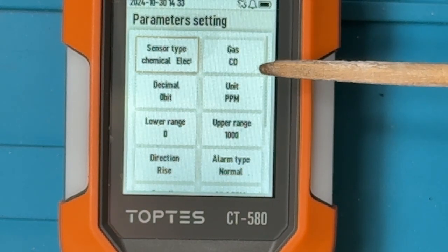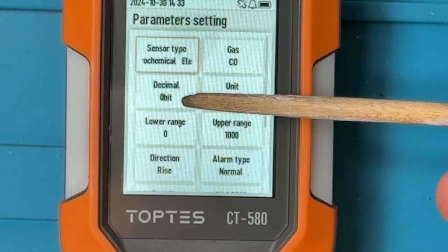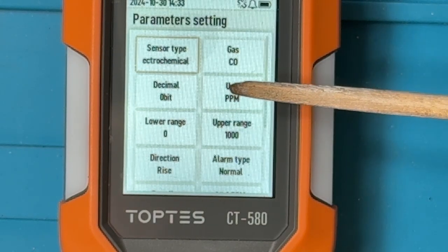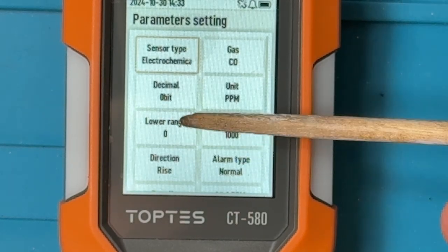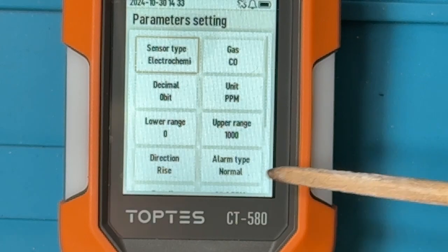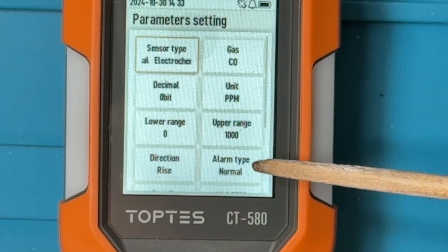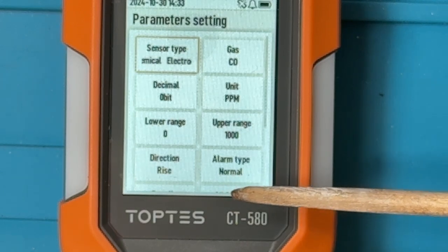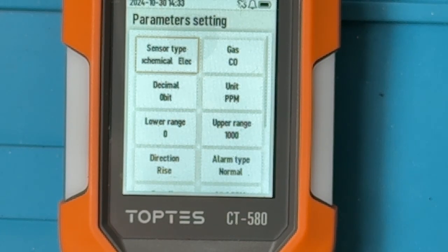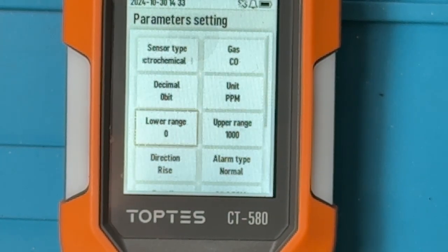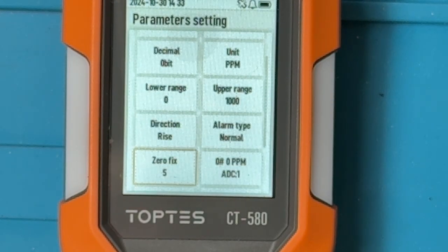So the sensors that we have, the information we have: a sensor type, so it's the type of the sensor. We have the type of gas that can be detected. We have the number of decimal places that this device operates with. We have the units that are measured with this device, the lower detection range, the upper detection range, the signal direction of the sensor, whether it's rising or descending, the alarm type. And so for non-oxygen sensors, the threshold is triggered when the value goes above a setting. For an oxygen type sensor, we would want to trigger the sensor when the value goes below a setting. And then a couple of other things here.